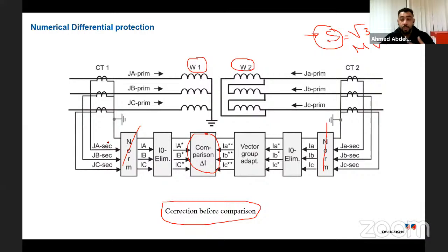Then I need to do something important. What is it? The I0 sequence elimination. What is the I0 sequence elimination? This is a challenge that can happen if I have a transformer with a star winding, and the star is grounded. What will happen? Let us see here. I have this star side, and I have an external fault here in this side.